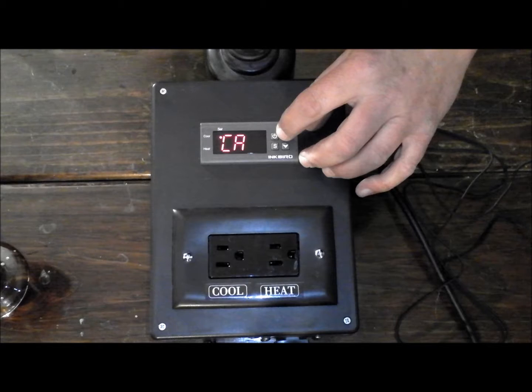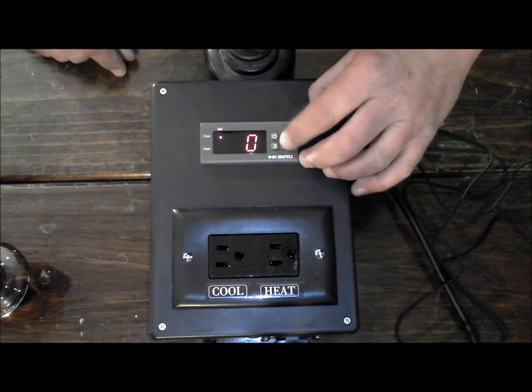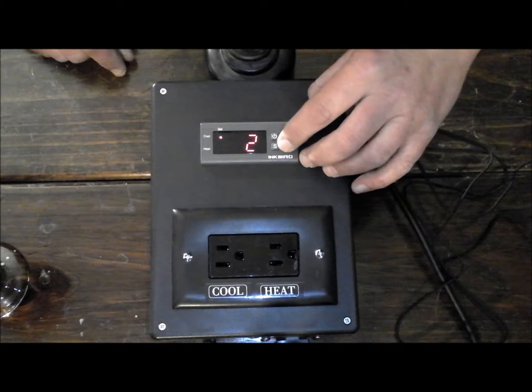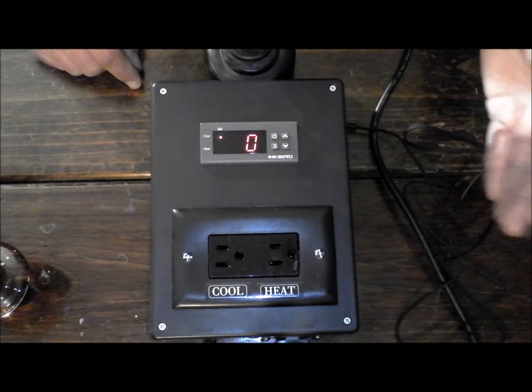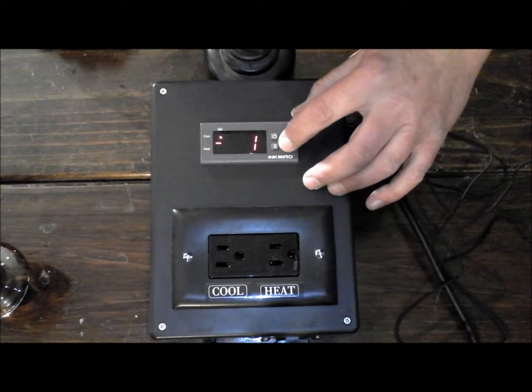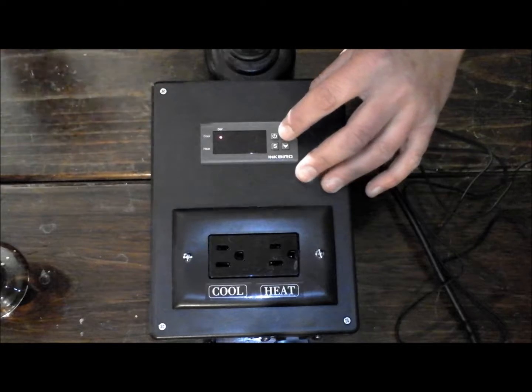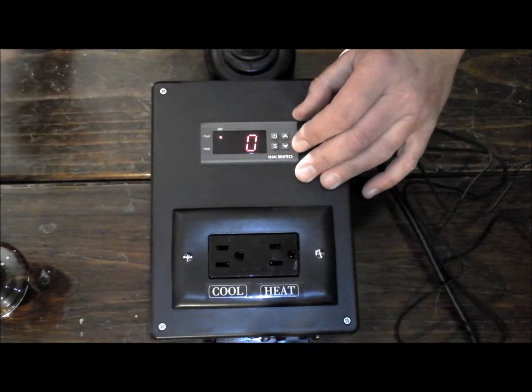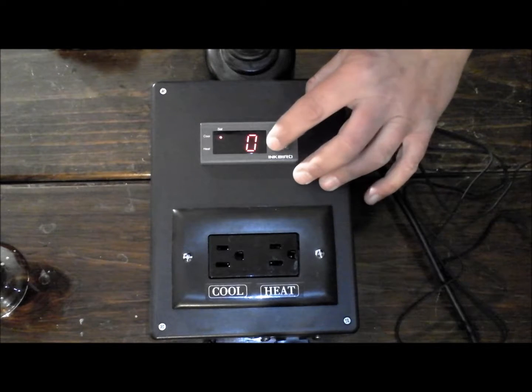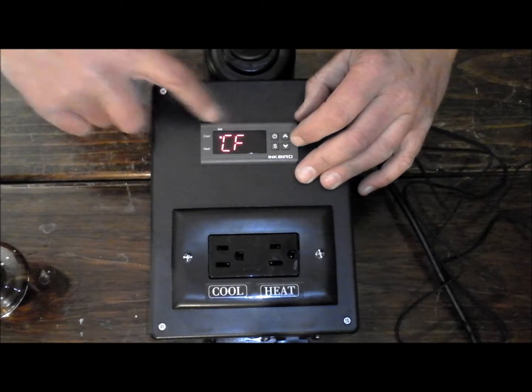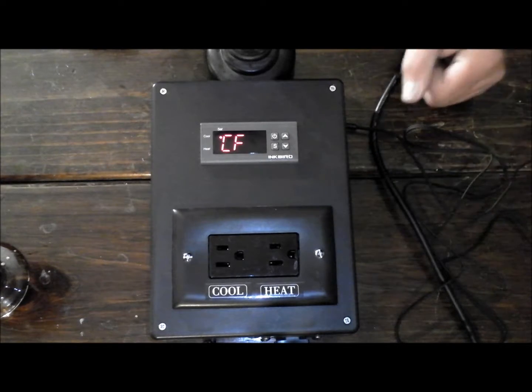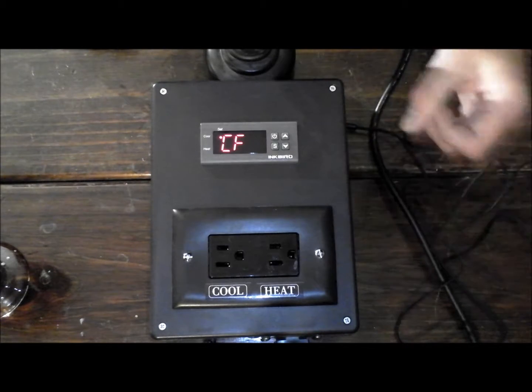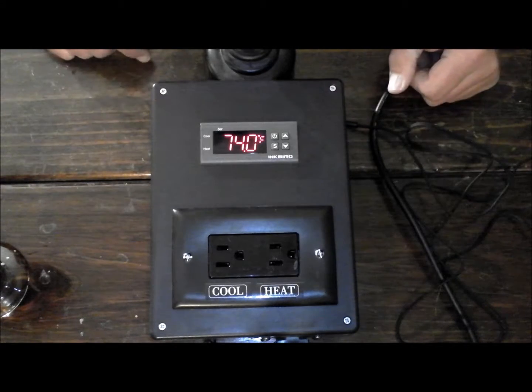The CA is your temperature calibration. What this allows you to do is either go negative or positive to calibrate the sensor if the sensor would happen to be off by, you know, say it's reading 2 degrees high, then you can subtract 2 degrees from the reading on there to give you a correct reading. And it compensates for any temperature that the sensor itself might be off. And then the CF switches between your Celsius and Fahrenheit settings. And if you just let it go for a few seconds without doing anything, it'll revert back to your temperature setting.